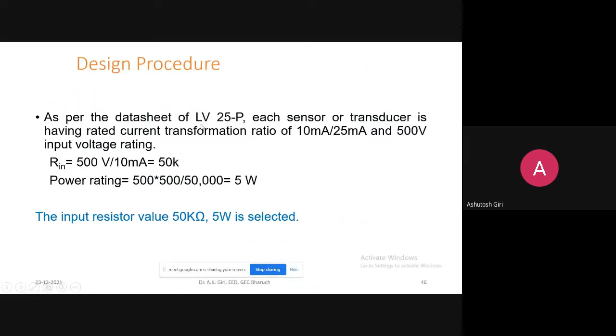LA55P is provided here with primary winding current. The limitation is the rated current value of 50 ampere. You cannot flow more than this. And suppose if line current is 10 ampere, then the corresponding output current is 10 milliampere.